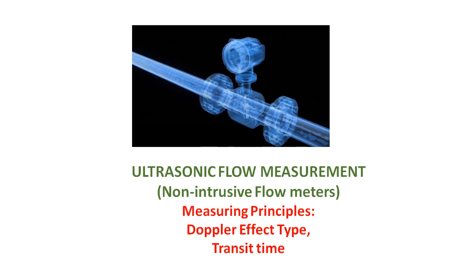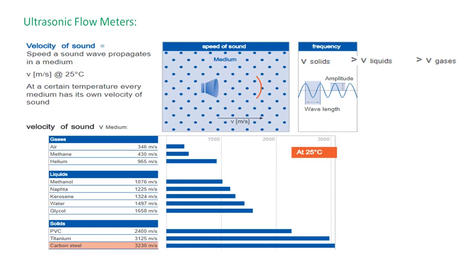The measuring principles that ultrasonic flow meters use are the Doppler effect type and transit time measurement for the measurement of flow rate. Ultrasonic flow meters use ultrasound, and the velocity of ultrasound depends upon the medium. The velocity of ultrasound is greater in solids compared to liquids and gases.